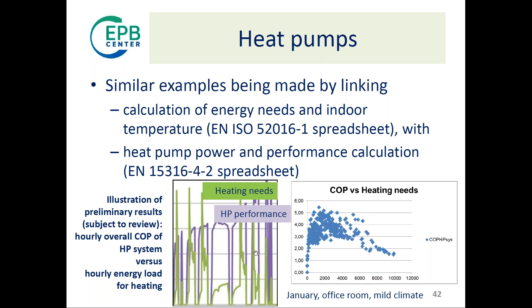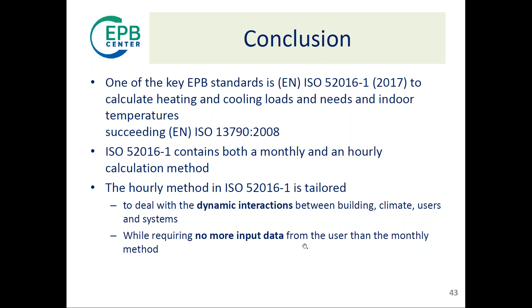So the conclusion is that one of the key EPB standards is this 52016 part 1 for heating loads and needs and indoor temperature. It contains both a monthly and hourly calculation method, and the hourly calculation method is tailored to be able to deal with the dynamic interactions between the building, climate, users and systems, and it requires no more input data from the end user than the monthly method.